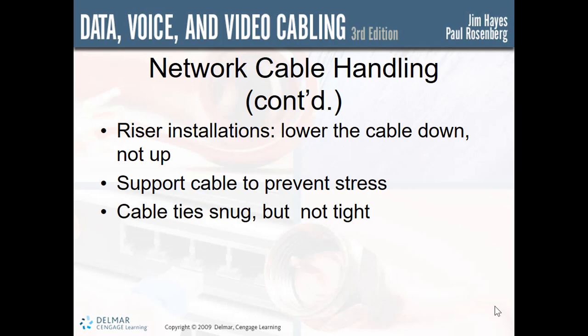On riser installations, try to lower the cable down. Don't pull it up. In case you're wondering why, when we pull, we end up with more weight on the bottom. As we pull harder and harder on the cable, it takes the twists out of the wire, which then degrades the wire's capabilities. Cables must be supported to prevent stress. Cable supports should not have sharp edges that may distort the cable. Cable ties must not be so tight as to distort the jacket of the cable. They are only used to prevent unnecessary movement of the cable. So snug is tight enough.